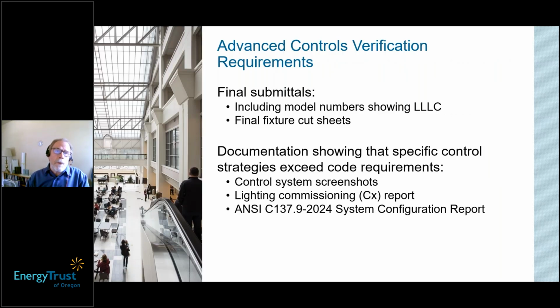The verification requirements come once your building is built, your system is installed, and it's theoretically been commissioned and is working. At verification, we'll generally go to the site and verify that the fixtures are installed and are in fact the model numbers that were proposed. We may also want to see some demonstration of the controls in some cases, and we'll want final cut sheets and submittals showing that the individual fixtures are in fact advanced LLLC.